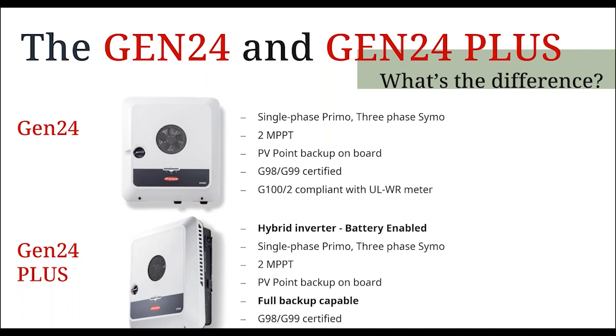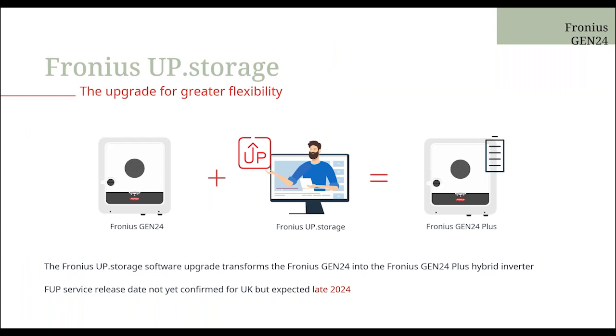So instead of having to put all their eggs in one basket and buying a more expensive hybrid inverter, they can start with the basic unit, and then in future they have the ability to use the Fronius Up Storage firmware update, which is a paid upgrade which turns the Gen24 into a Gen24 Plus. This means there's no hardware changes. It's purely the paid software update and then connecting the battery. It means you don't have to swap a standard inverter in and replace it with a hybrid device. The one unit has all the connections, all of the hardware. It's purely that software license that will change.